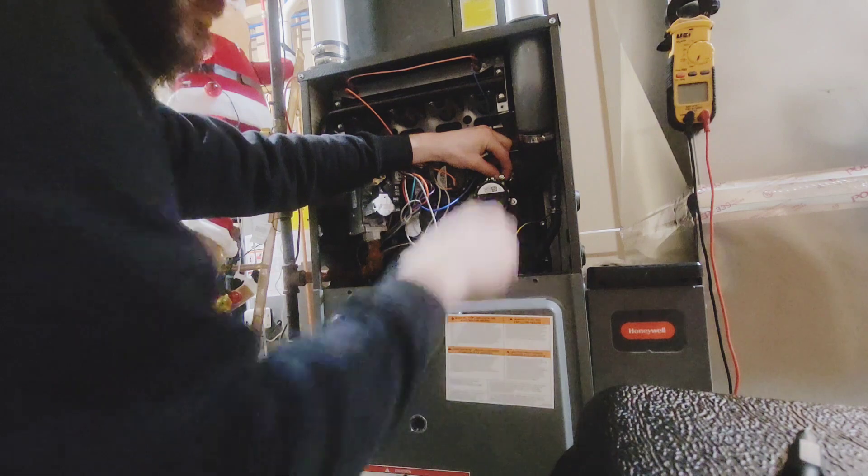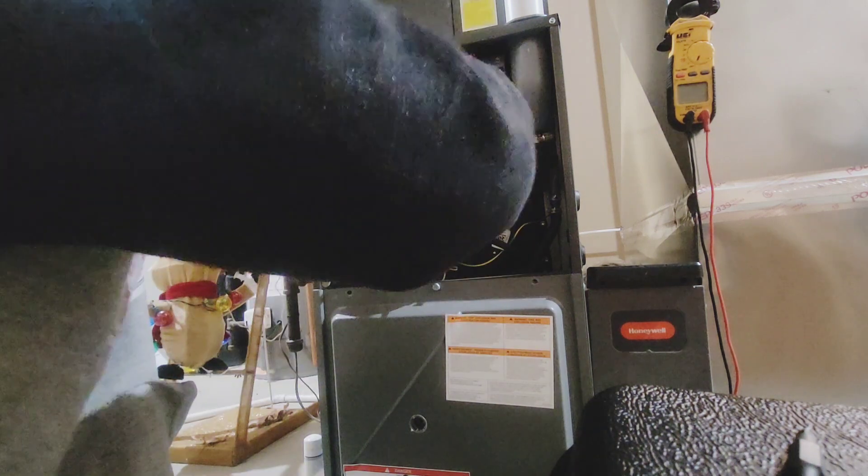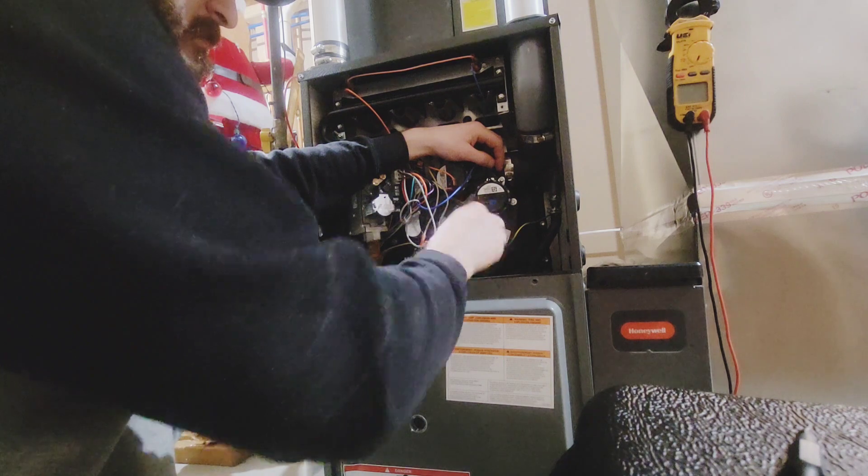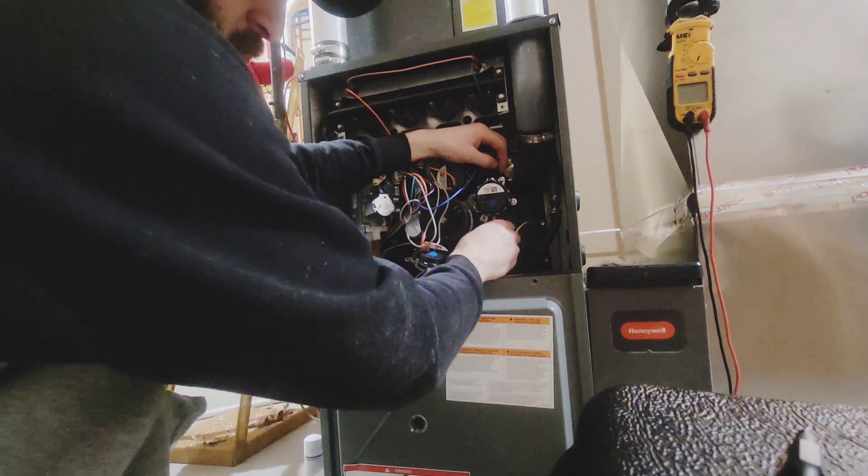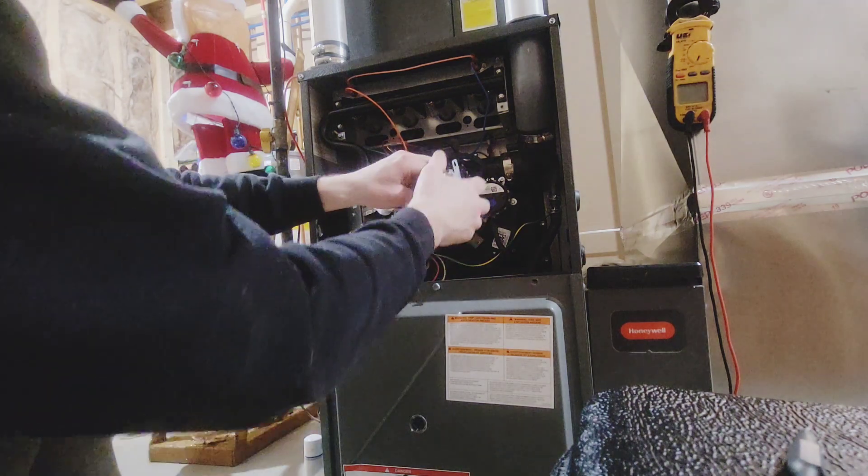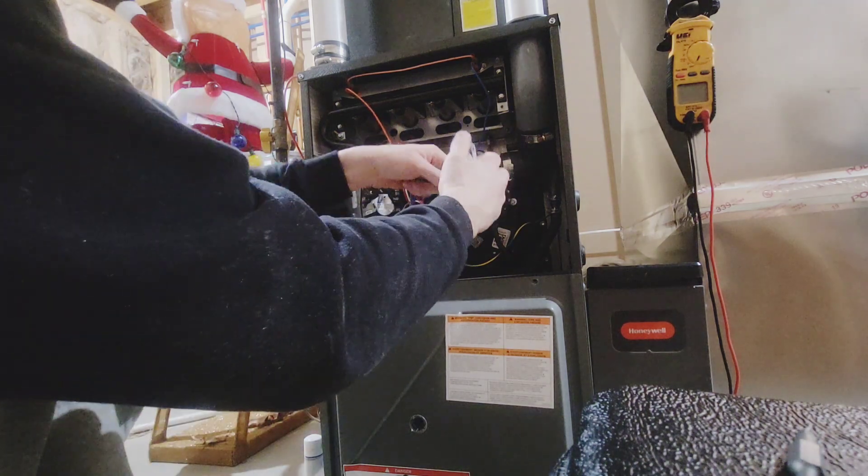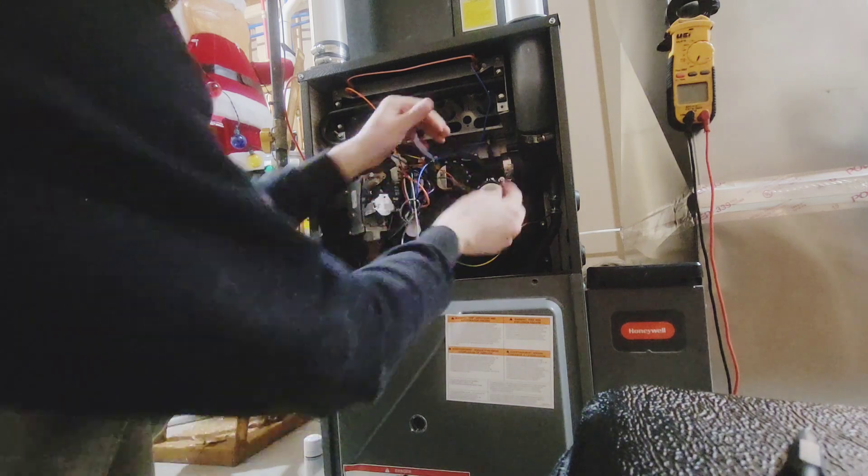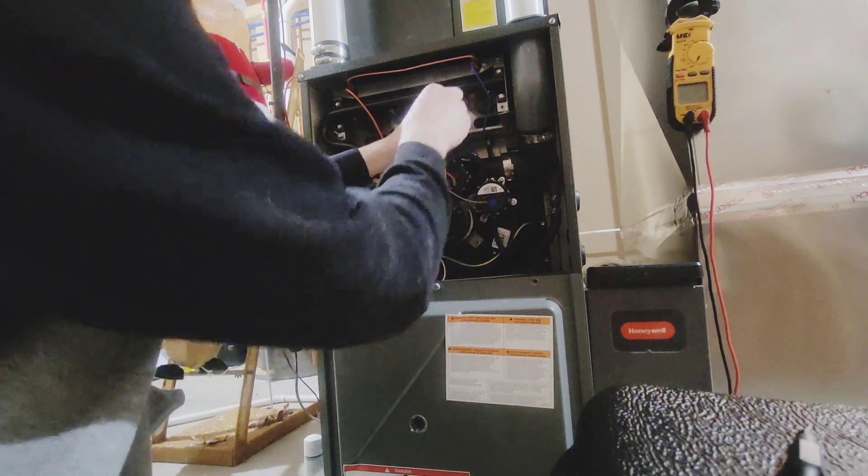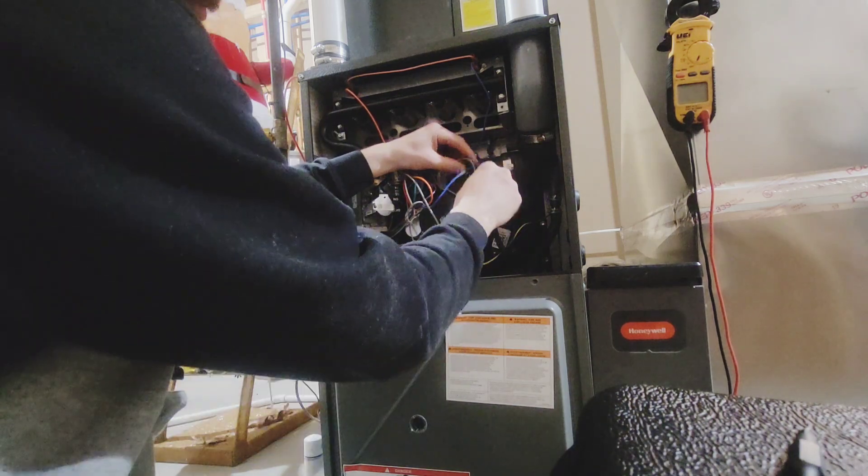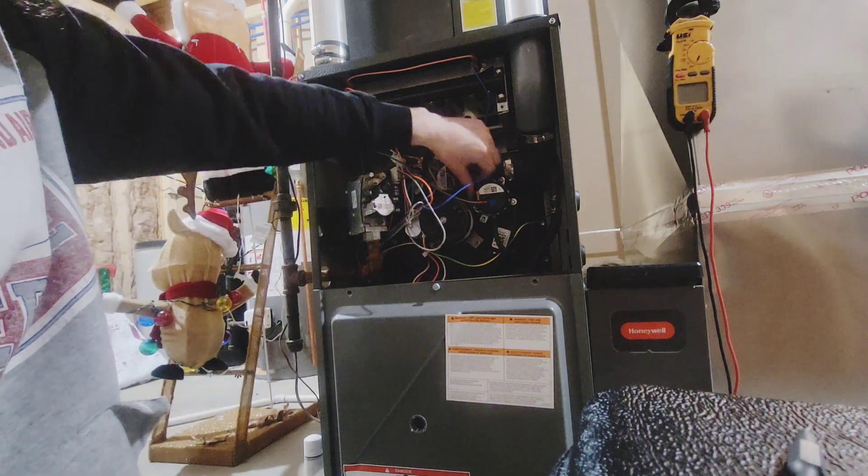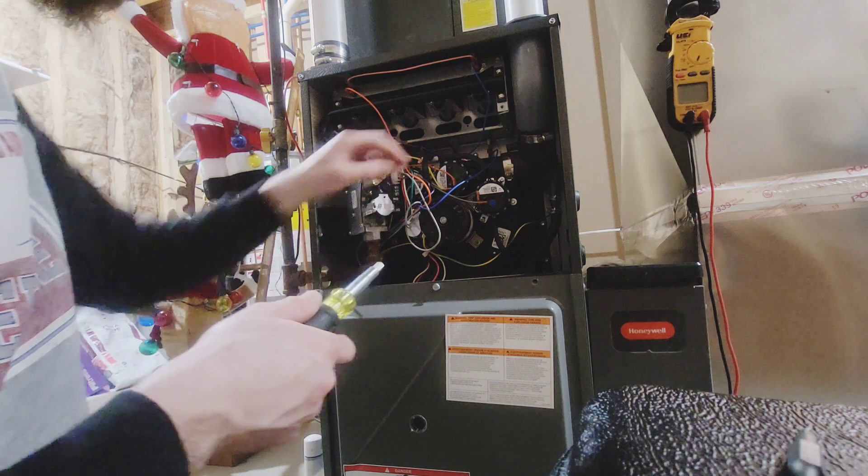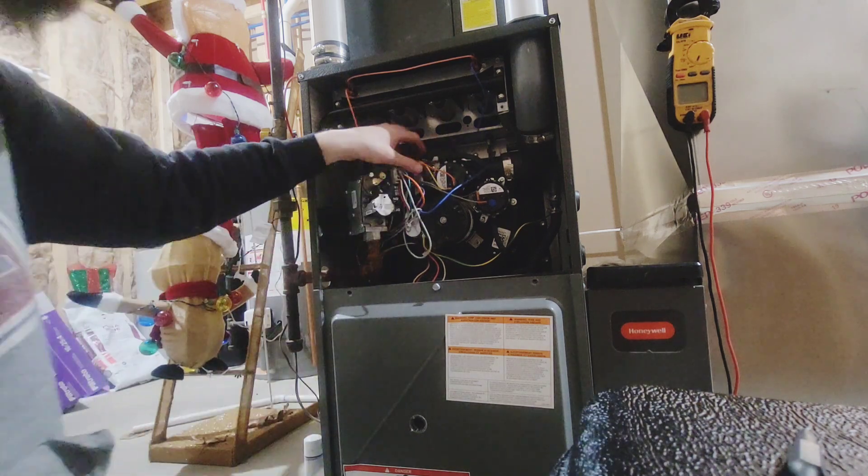So we are tightening this up right now. And that bottom screw, there is one on top, one on bottom. Pull our wires off of our old switch. Pretty simple plug and play. So you get a lot of companies that say, oh, you got a bad switch, let's just replace it. Well, this usually goes a little bit further in depth than that. It's usually a drain line issue or venting issue. There's a lot of variables into it.